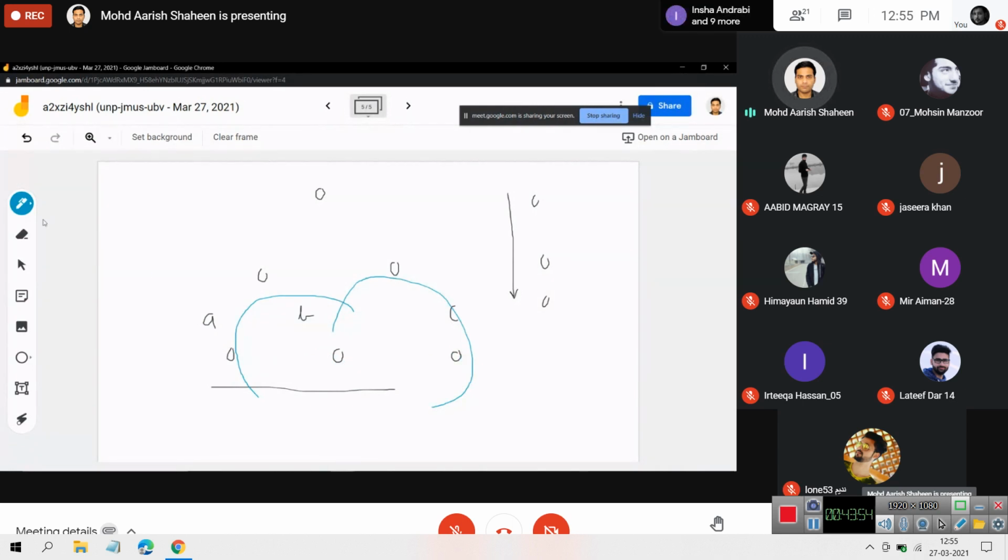But if you look at the mutual impedance between phase A and phase C, the separation is twice as much. So one would expect the mutual impedance to be substantially smaller. Okay? On the other hand, if I look at this system here, all the three phases are equidistant. They are present at the vertices of an equilateral triangle. Here the mutual impedances are the same.